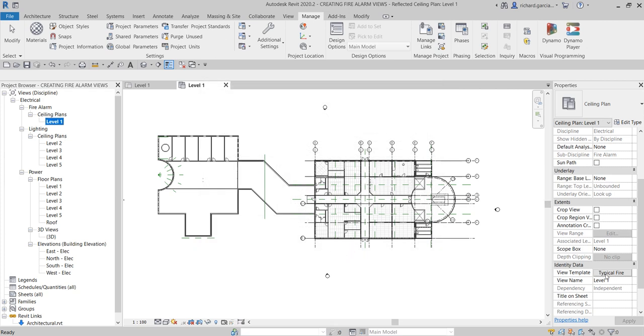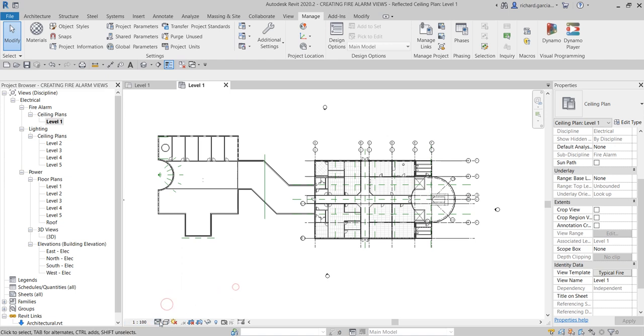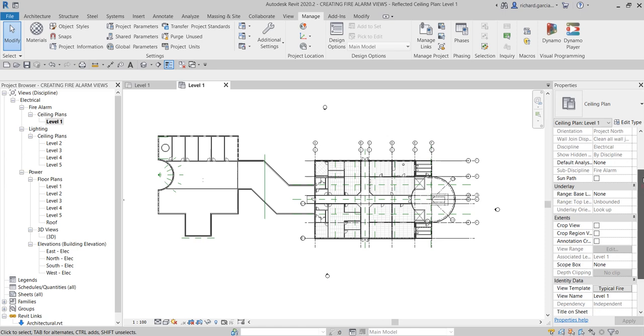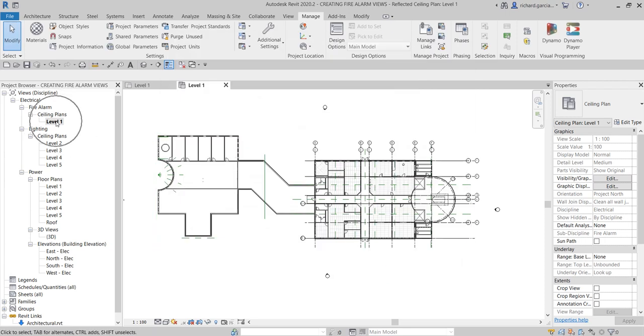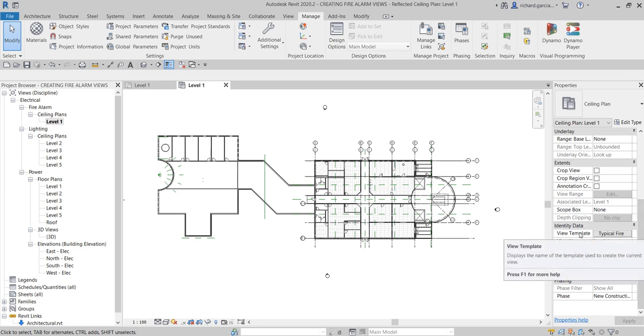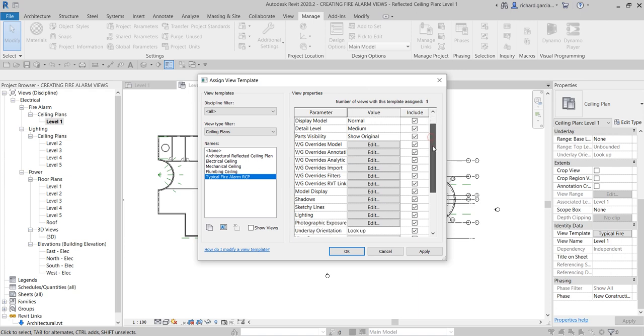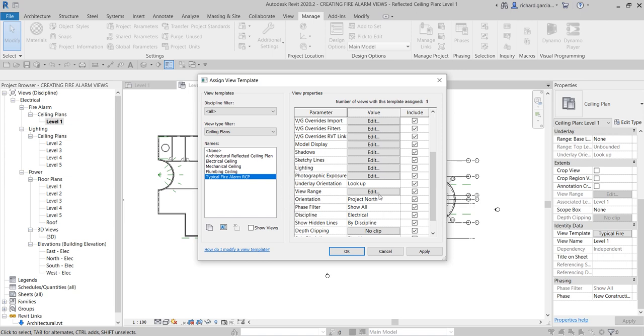The typical Fire Alarm RCP view template is now applied to Level 1. You'll notice that you can no longer change the scale, detail level, graphic display settings, or visibility graphic overrides directly — because the view template is controlling those. To modify view properties, you go to the view template, click the applied template, and make changes there. For example, to change the view scale you update it in the template. You can also uncheck properties like View Range if you don't want the template to control them.